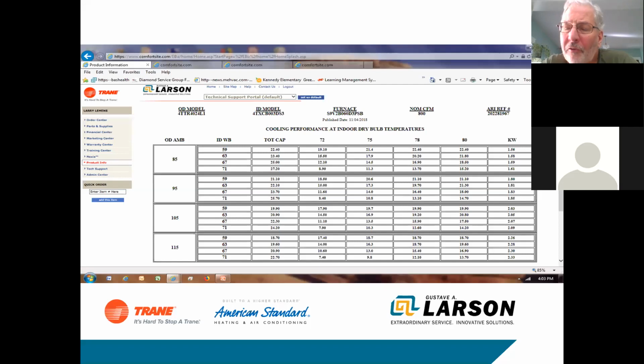There's also a sensible latent split, okay? So just remember, when you're selling an air conditioner, you're putting in an air conditioner, that if it's 85-degree outdoor and the wet bulb indoor is 71, in other words, it's pretty humid, at say 78 degrees, I'm getting 13,000 BTUs of sensible cooling out of that unit. I'm not getting the full 2 tons. I'm still getting 27,000 BTUs, but 13,000 is sensible. The rest is latent. It's all working on humidity.